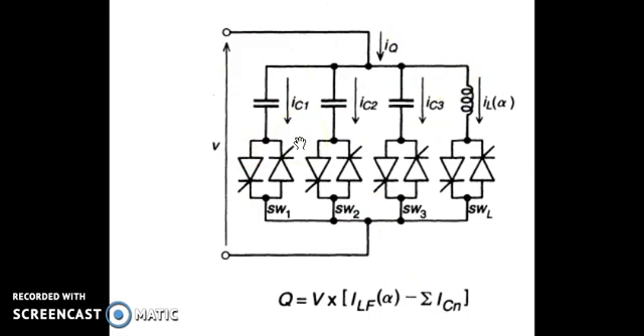This combination of thyristor switched capacitors and thyristor controlled reactors is called an SVC — a Static VAR Compensator. The combination can vary: it does not need to be TSC plus TCR specifically. It can be a set of fixed capacitors plus switched capacitors plus a controlled reactor, or other configurations. Typically, the reactor is a single entity while multiple capacitors are used.